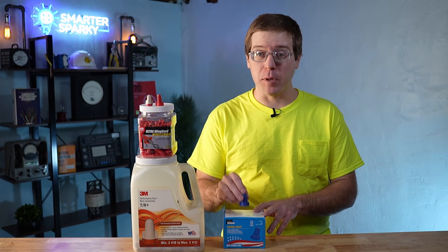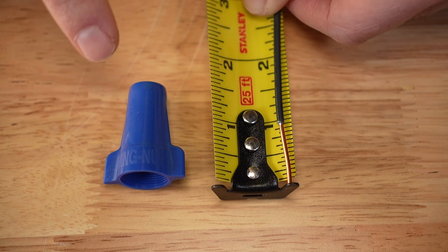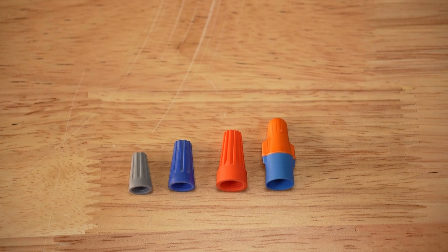For larger wire nuts like this big blue, the manufacturer recommends 7 eighths of an inch of insulation stripped out. Naturally, smaller wire nuts are going to require a shorter strip length.